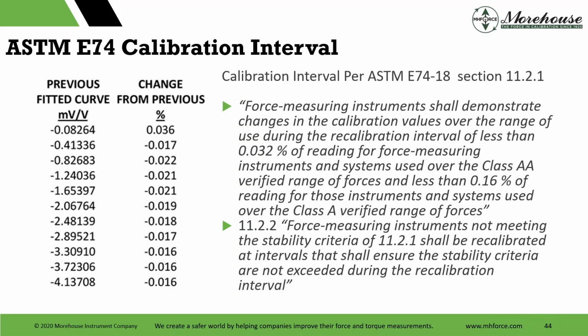Calibration interval, I wanted to talk about this. I hit on it earlier. 11.2.1 basically says force measuring instruments shall demonstrate changes in calibration values over the range of use during the recalibration interval of less than 0.032% of reading for force measuring instruments and systems used over the class AA verified range of forces, and less than 0.16% of reading for those used over the class A verified range of forces. 11.2.2: force measuring instruments not meeting the stability criteria of 11.2.1 shall be recalibrated at intervals that ensure the stability criteria are not exceeded during the recalibration interval. In this scenario, our class AA first point doesn't meet the 0.032, though that was 100 pounds. We're okay because our class AA range is 175, which then would meet.